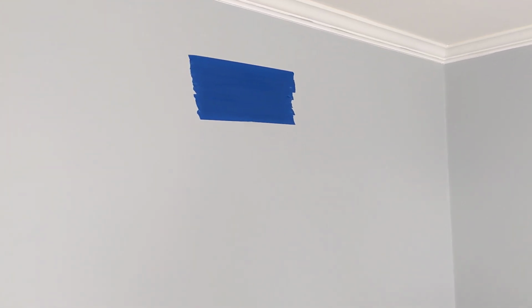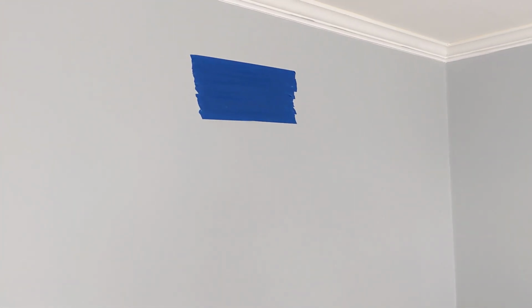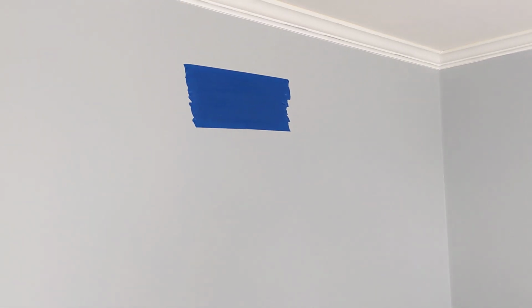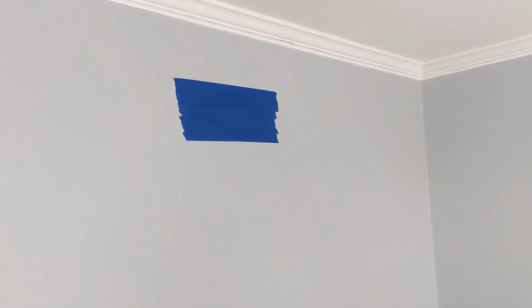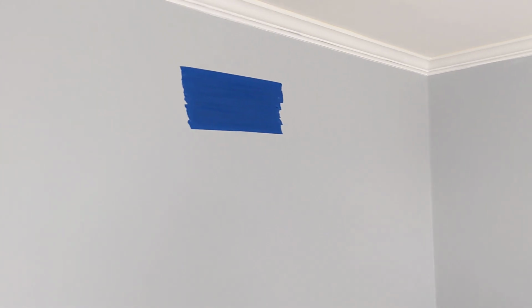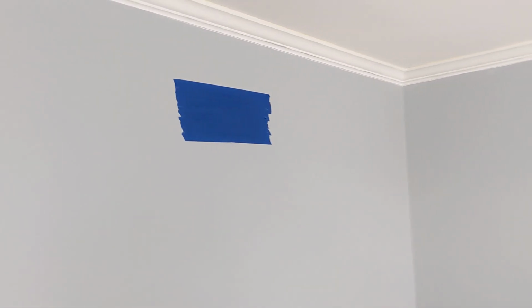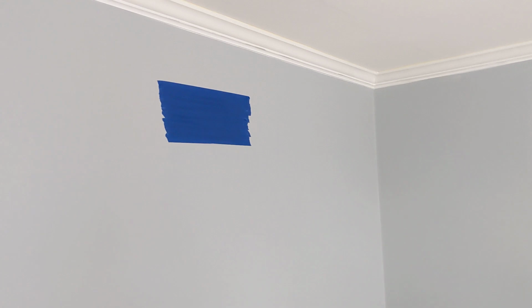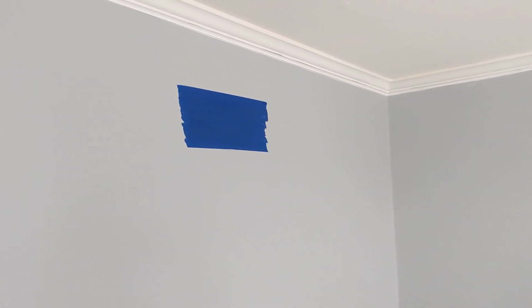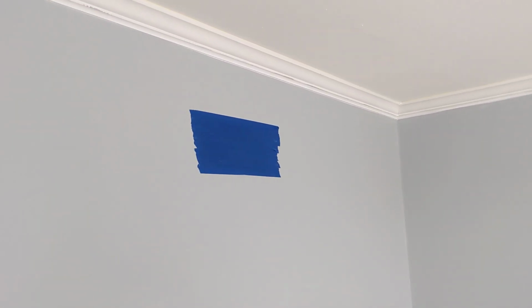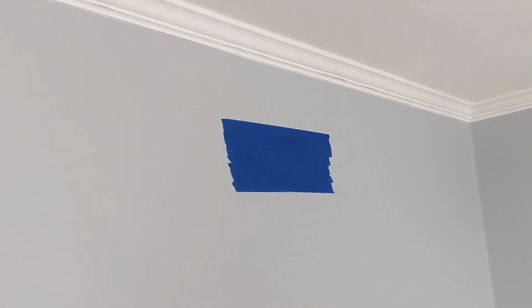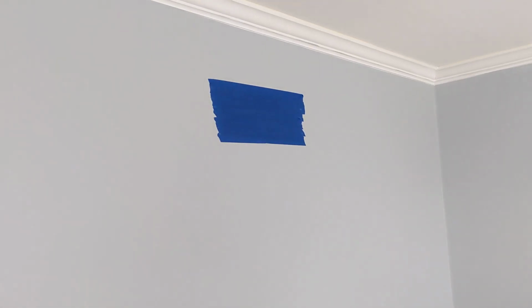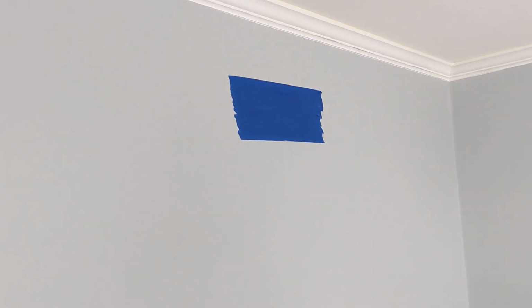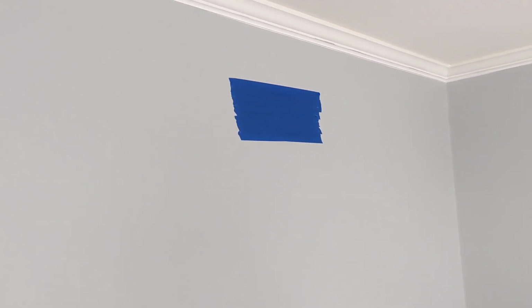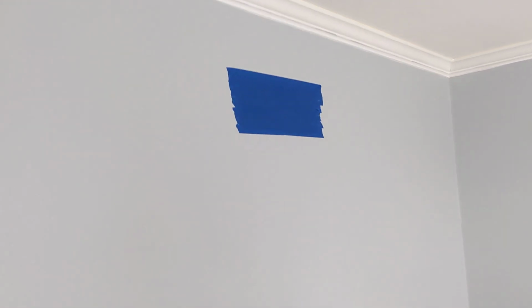We'll start up on the second floor, at the farthest point of the house, work our way through the different rooms of the second floor, then come down to the first floor, work our way through, and then back to the laundry room, do the unit, and then the same process for the supply. So here's a typical return ductwork where the vent's been removed. Painter's tape is set up to block that run of ductwork off, so that we can isolate individual sections of ductwork for our cleaning, our whip system, compressor cleaning process. So this one's blocked off, and then I'll show you over here.